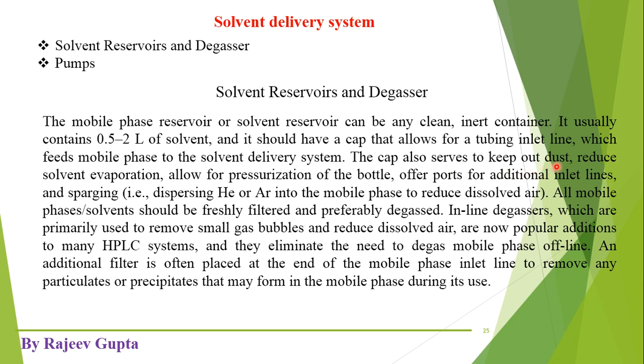Also these caps keep the dust out. They offer ports for additional inlet lines and sparging, dispersing helium or argon into the mobile phase to reduce dissolved air.